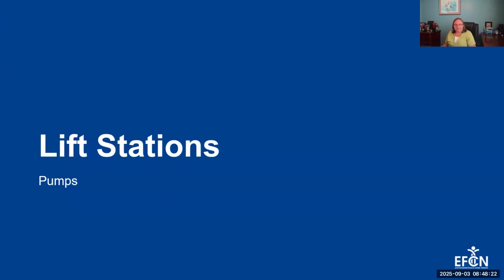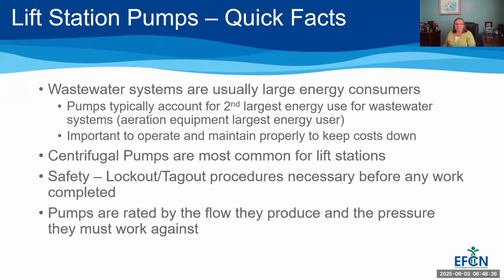So next we're going to take a look at lift station pumps. These are just a few quick facts I wanted to throw out before we get into the details of the pumps. Wastewater systems are usually very large energy consumers. In any community, a wastewater plant is one of the highest users of electricity of anything, other manufacturing facilities, obviously houses. So pumps typically account for the second largest energy use for wastewater systems. Your aeration equipment is usually the largest energy user, but it depends on how many pumps you have and how big the pumps are. So it's important to operate and maintain your pumps to keep your energy costs down.